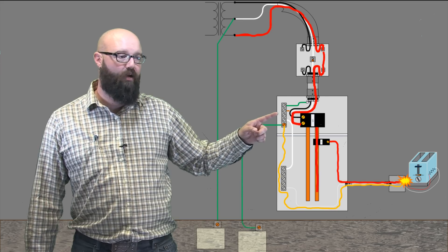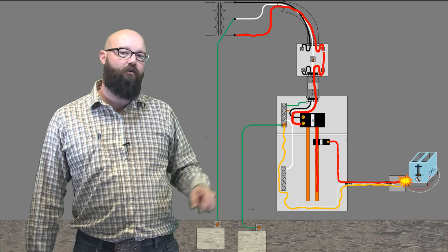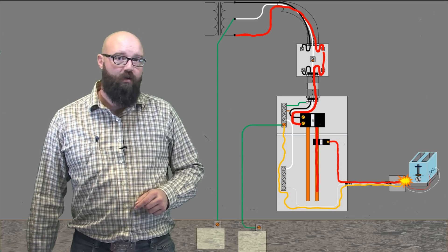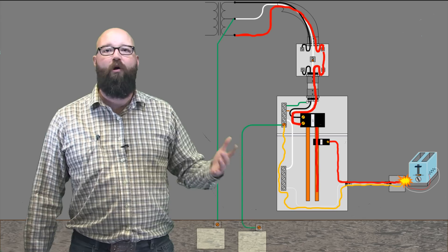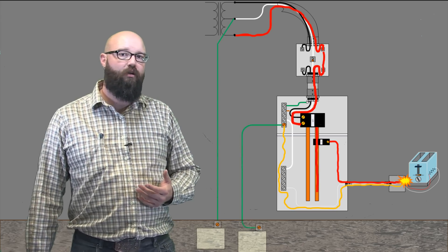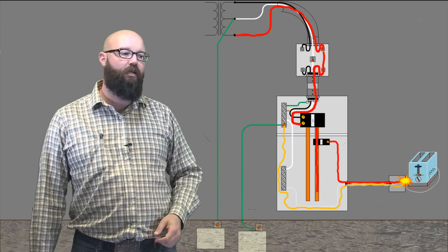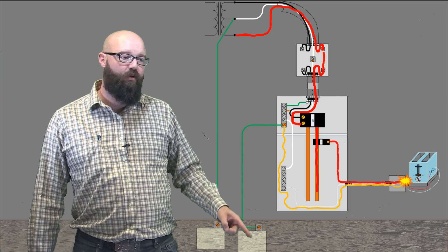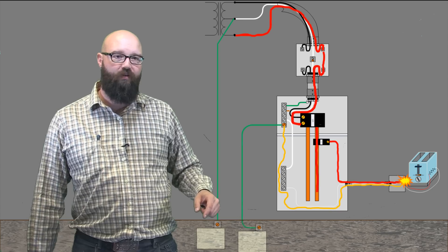Now remember, we lost the neutral conductor. But we do have this little green conductor here. We call that our service raceway bonding jumper. The intent of this is obviously to bond the service raceway. But it also gives us a backup path in a situation like this where we lose the neutral. That fault current still has a place to go.